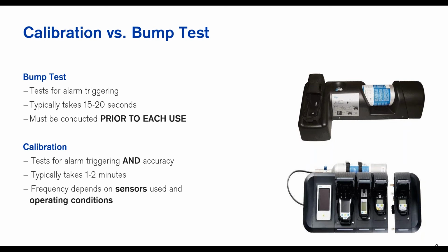Yeah, absolutely. And I see that a lot myself, or saw that a lot myself with refining as well. We used them quite frequently. And our routine at that point was calibration weekly, obviously a bump test every shift. But it depends and it varies, but you obviously want to make sure that everything is functioning properly, because you certainly don't want to get out to a potentially hazardous area and the meter not be performing as expected. Exactly.